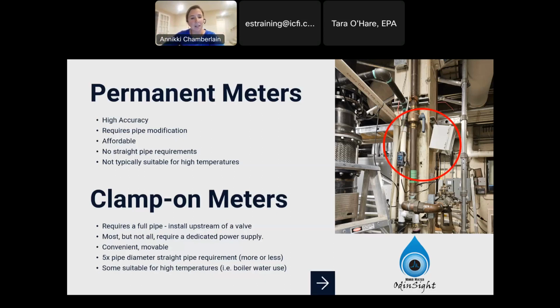So that's very convenient. The specs are a 5 times pipe diameter of straight pipe, upstream and downstream. We'll look at that. So that's good to know and something to consider, but I'm just a big fan of testing it first because they work pretty good in most situations, but more or less that is the requirement. And then some are suitable for high temperature. The bigger ones can go up to almost, I think, a little over 200 degrees, and smaller ones, you just have to get a way to separate them. They make high temperature clamp-on meters. So that's very nice, especially for a boiler blowdown or boiler condensate return. So as with all of life, there's trade-offs, but those are the main nuances.